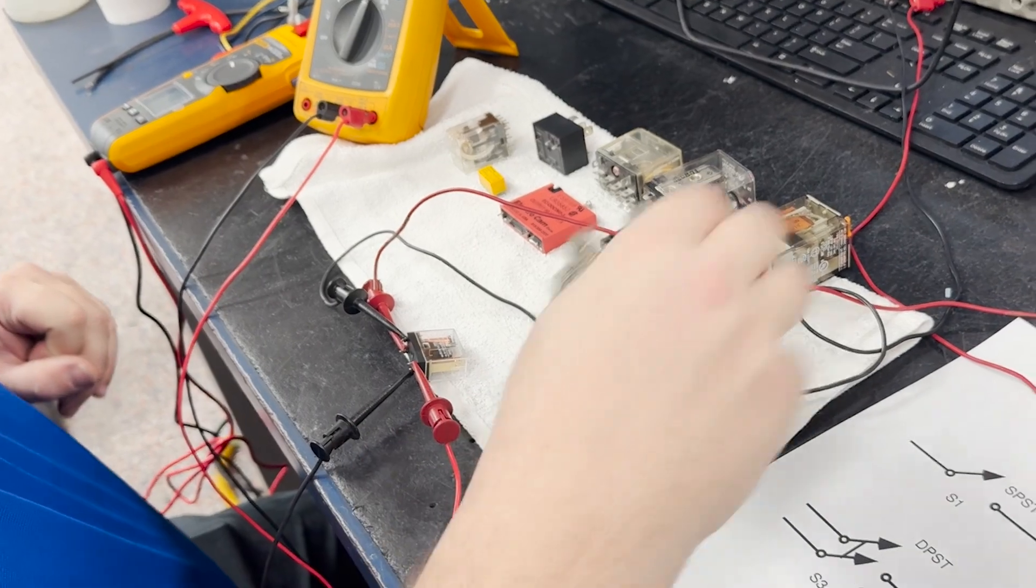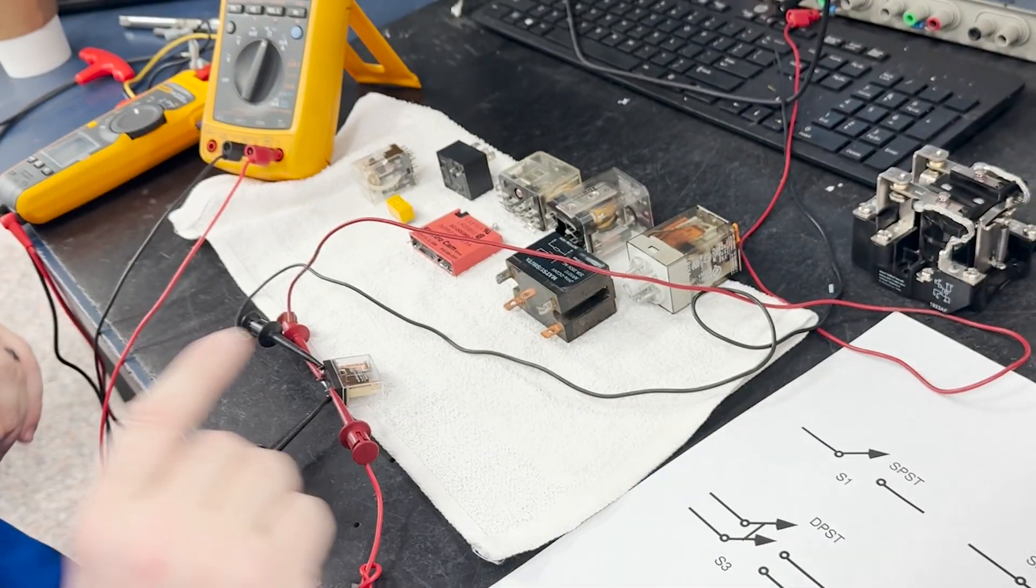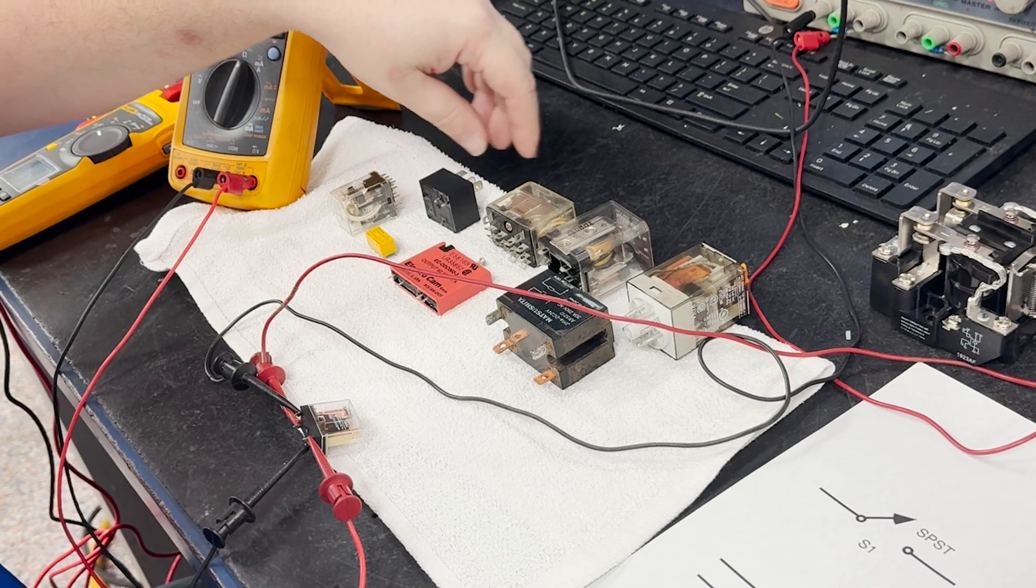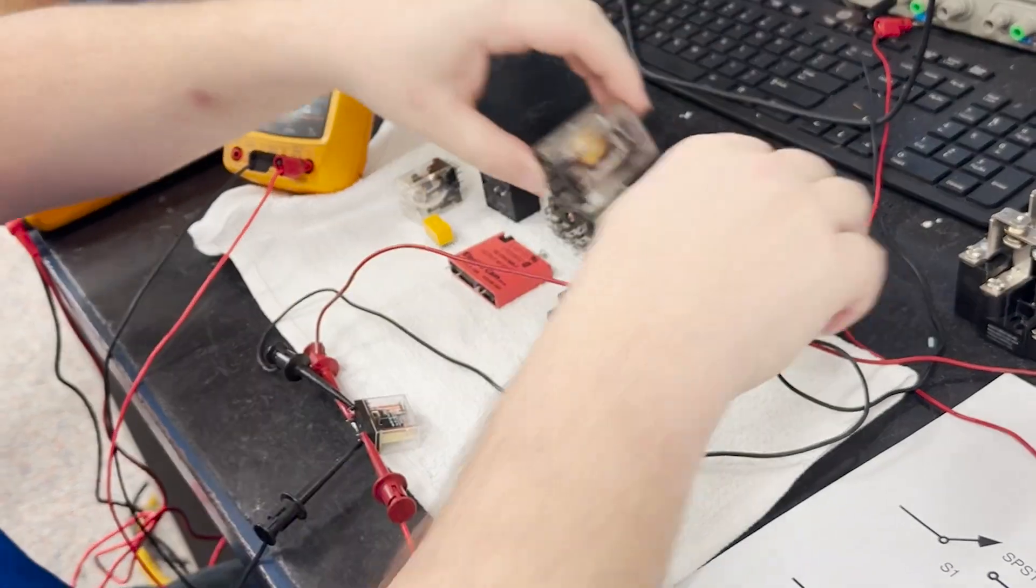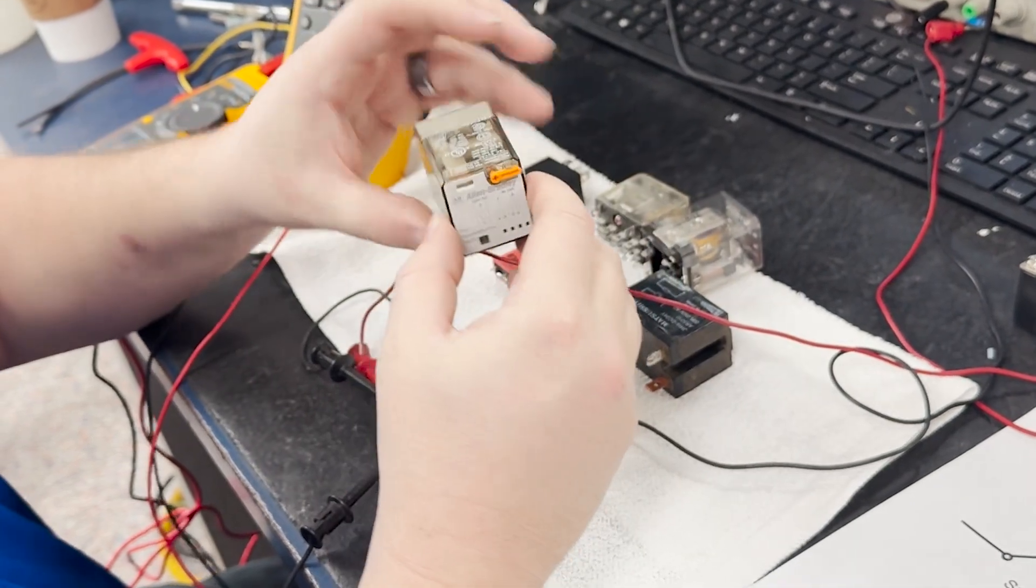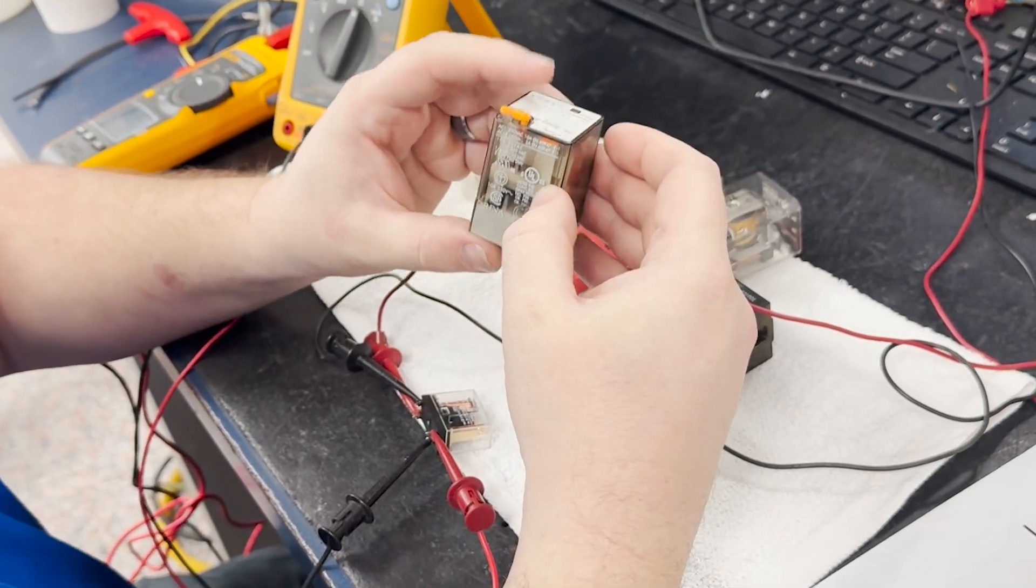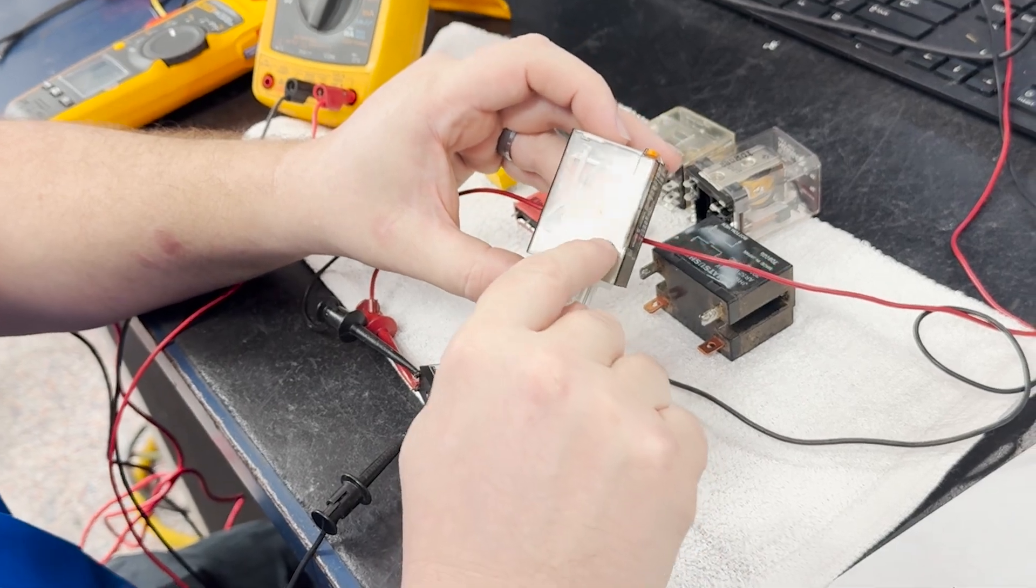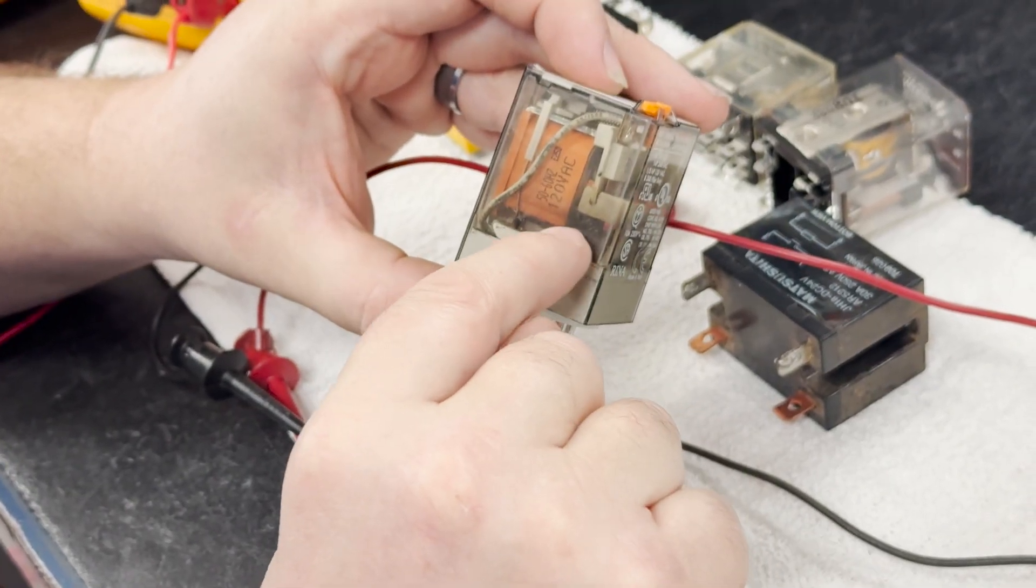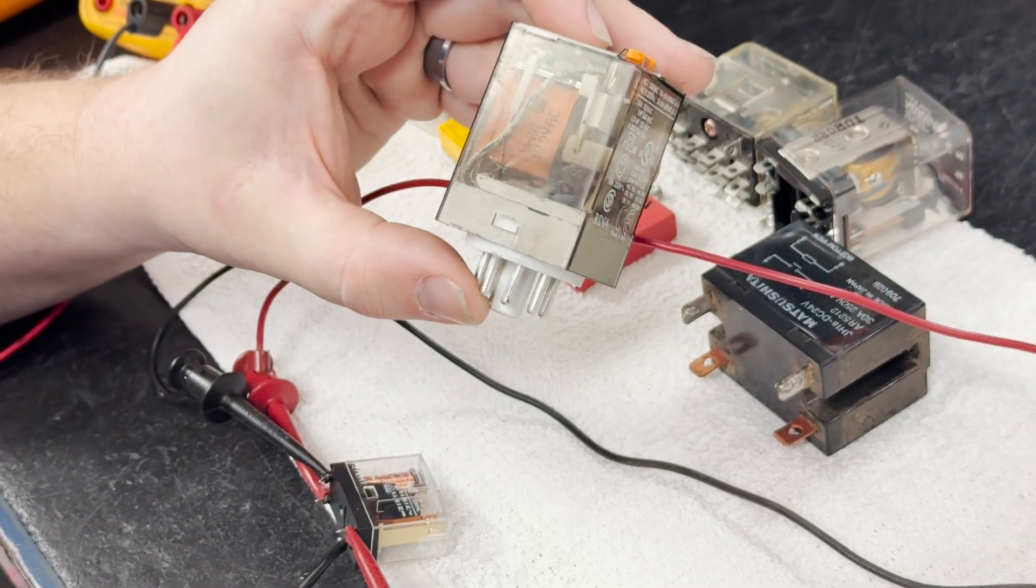So now we will go over one of the most common failures we see when it comes to relays, which is carbon buildup on the contacts. So here we have a relay that we found to be failed, and we can see that the reason for the failure is this high buildup of carbon on the actual contacts. So I will demonstrate this relay and show you what we mean.